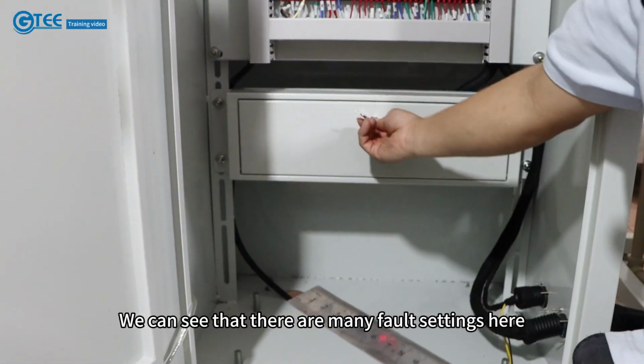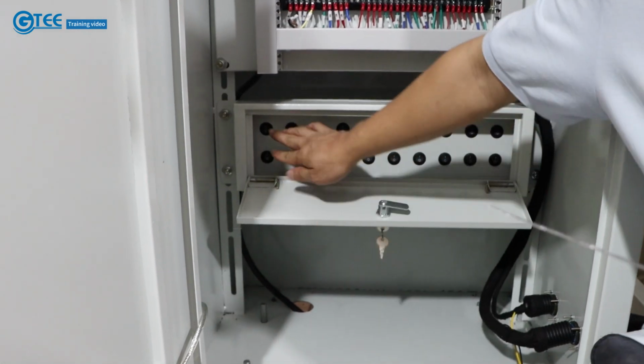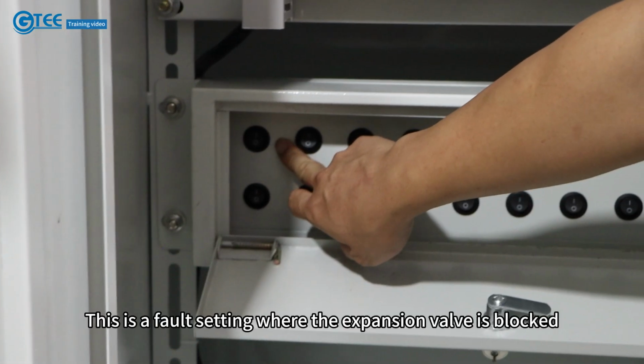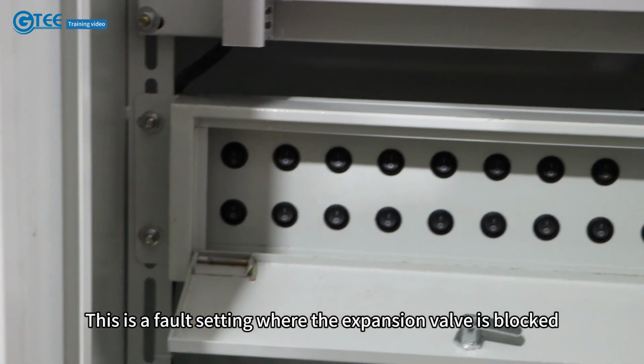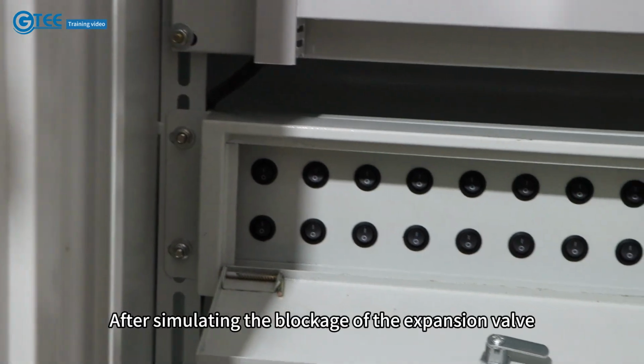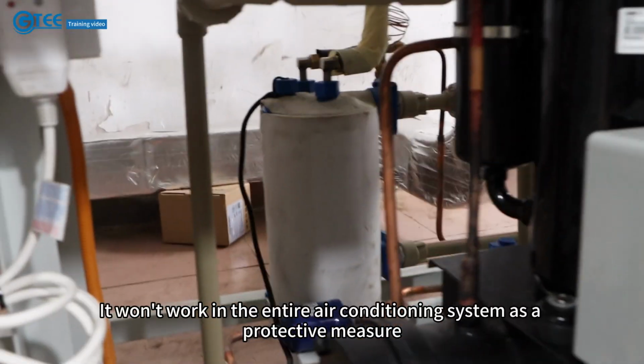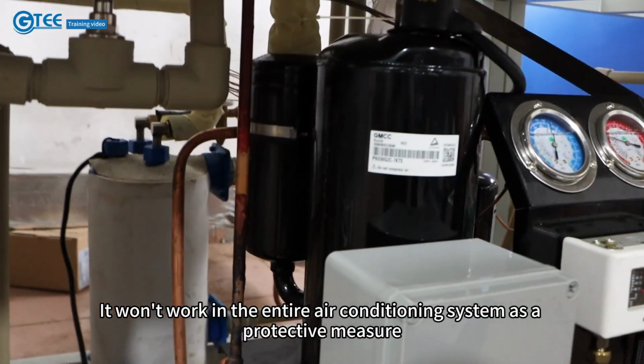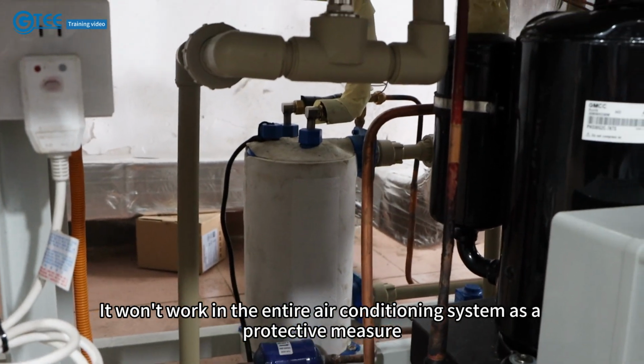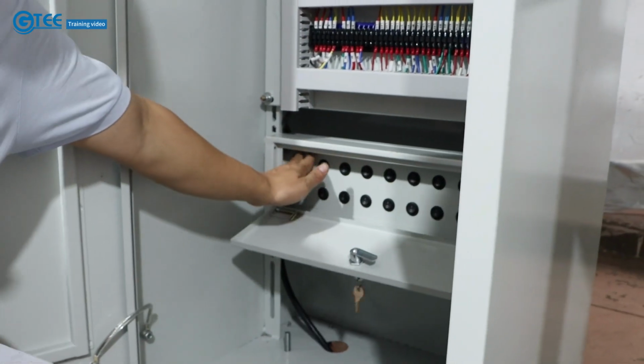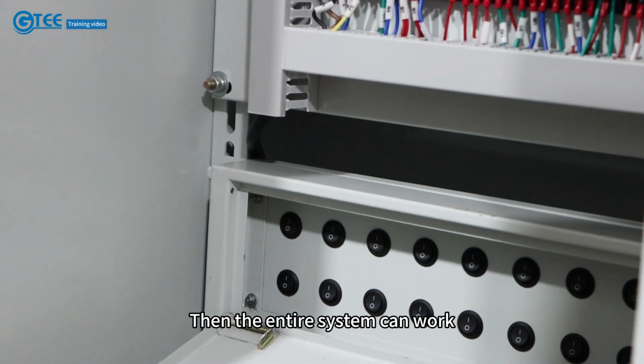Next, let's set up a fault. We can see that there are many fault settings here. Let's take the first malfunction as an example. This is a fault setting where the expansion valve is blocked. After simulating the blockage of the expansion valve, the entire air conditioning system won't work, as a protective measure. We will restore the fault switch and the fault will be eliminated. Then the entire system can work.